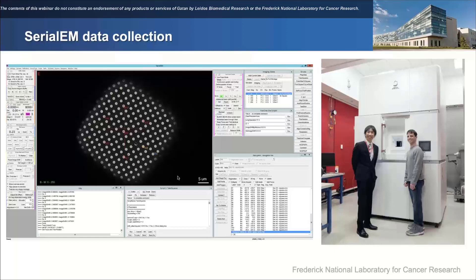Me and Taku always talk about improving data quality and getting to higher resolution — different data collection settings, camera frame rate, correlated double sampling mode, making sure the room is as quiet as possible so that's not a resolution-limiting factor. Our goal was to take the 1.8 angstrom result and make it better. I'm happy to report that 1.8 angstroms is not the limit for this microscope.